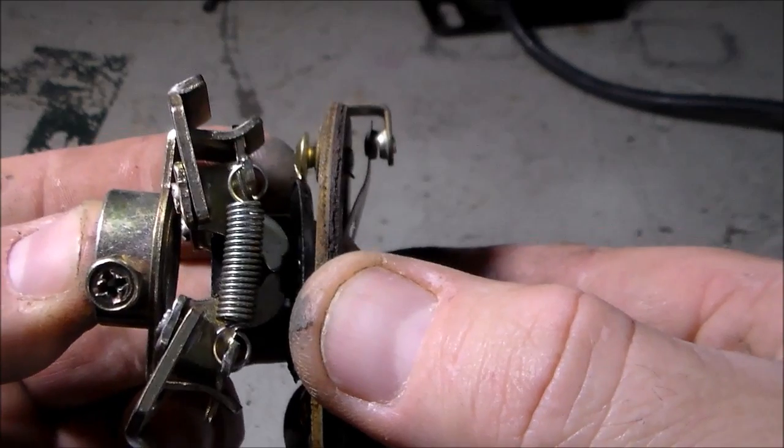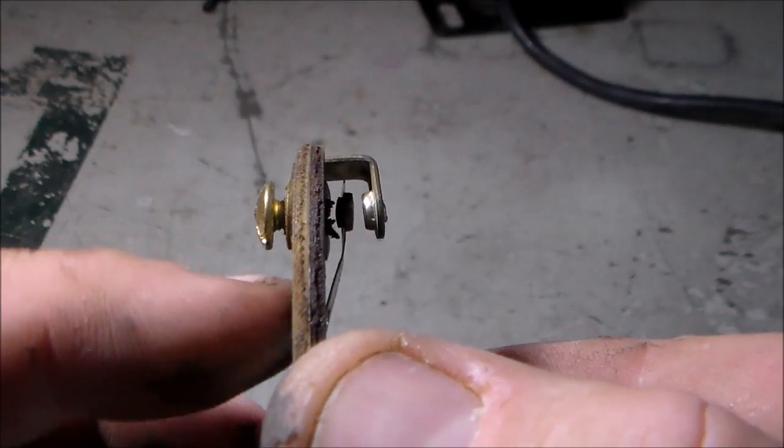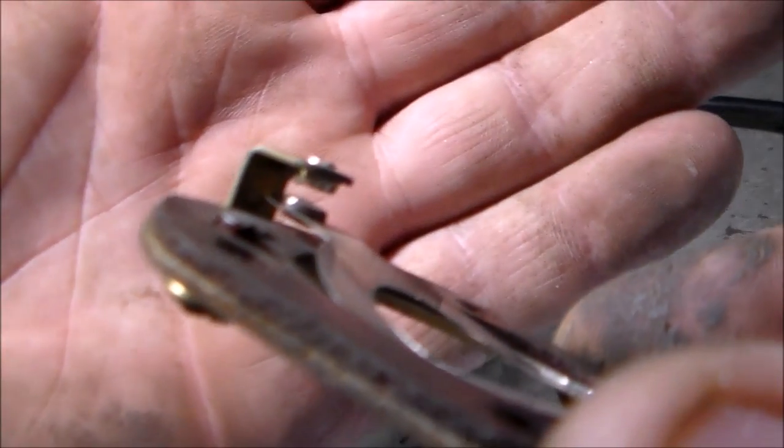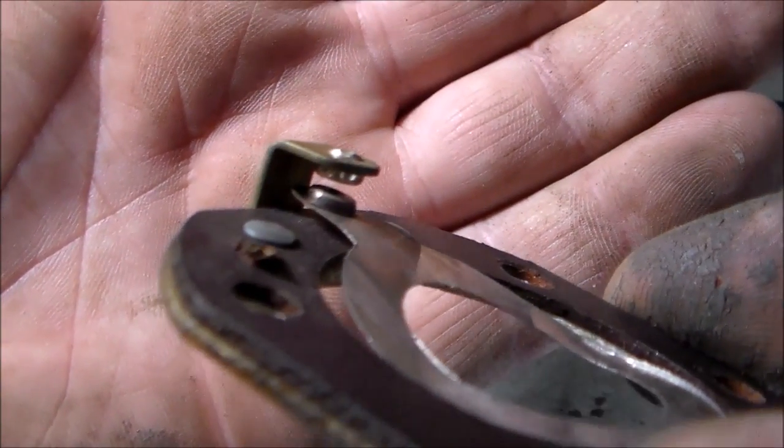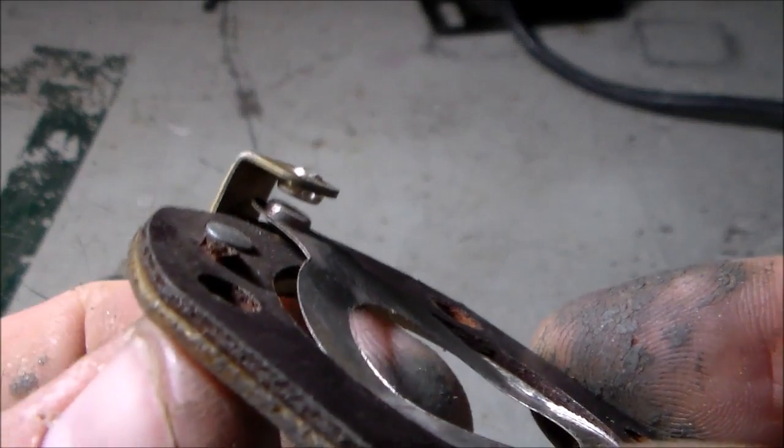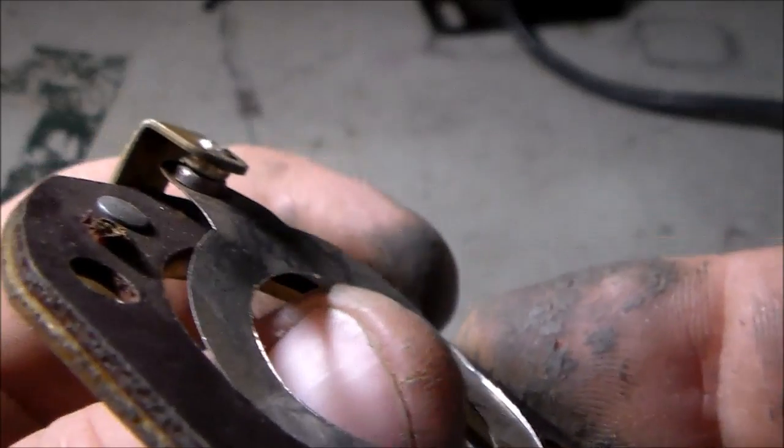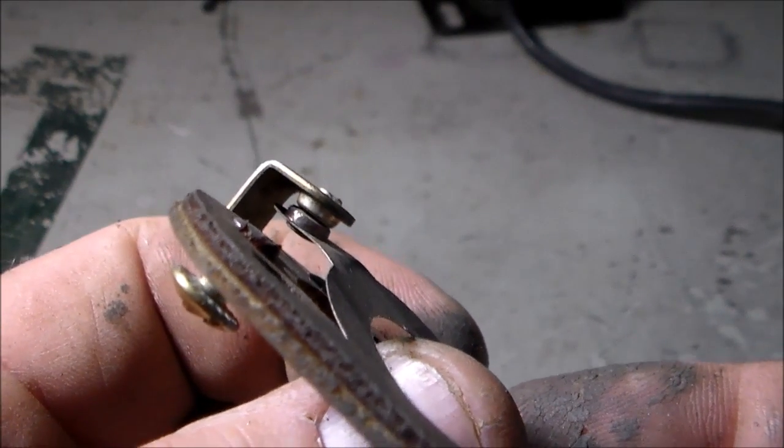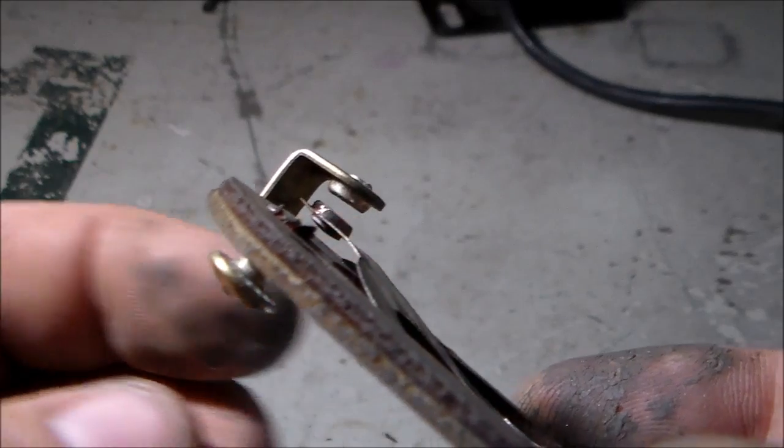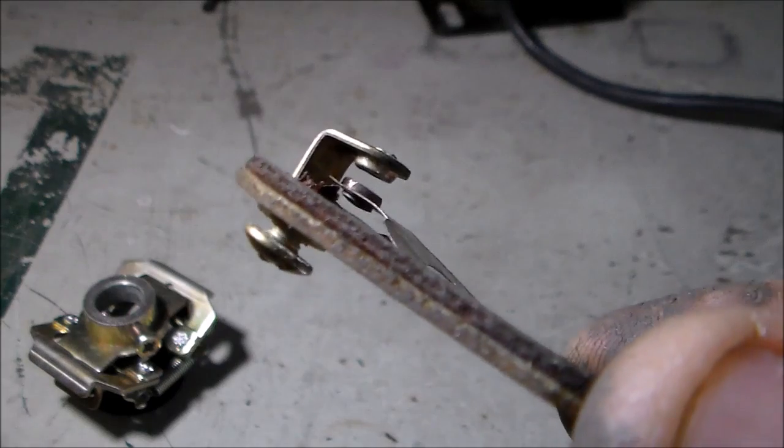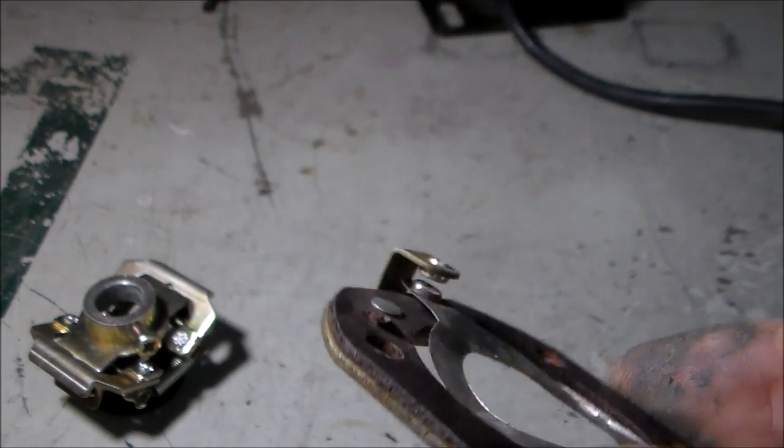I don't know if that helps any, but what had happened was those surfaces there, which I don't know if it's focusing, but they had got a little arcing or corrosion or something. And they were just stuck. They were stuck like that all the time. And when I took it apart, I popped them open and I took a little piece of real fine sandpaper and cleaned both sides. And from that point on, it seemed to work fine.